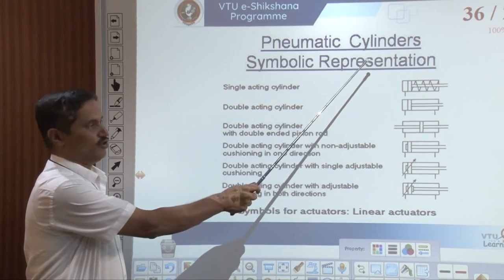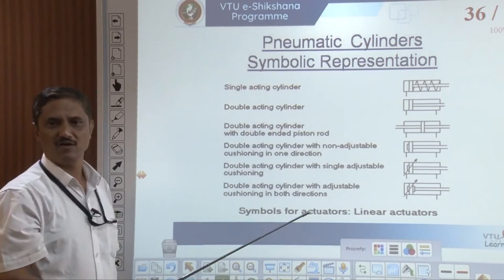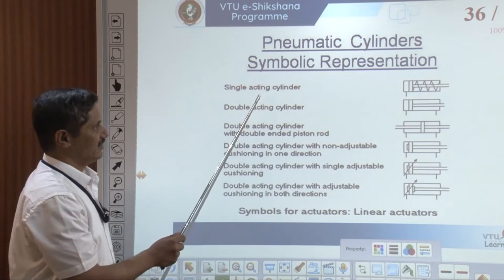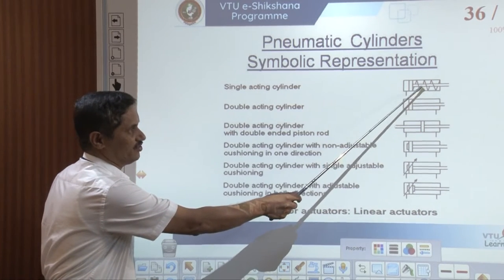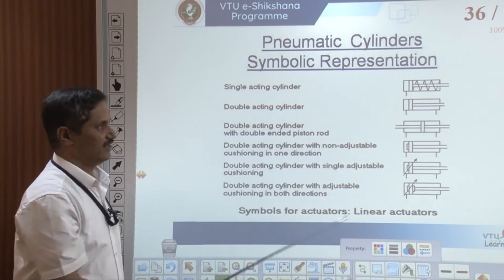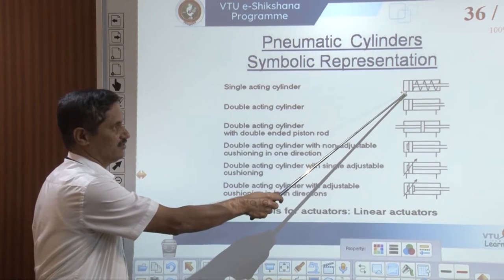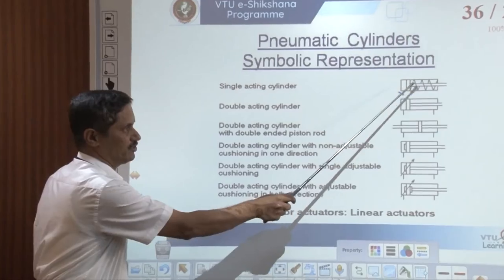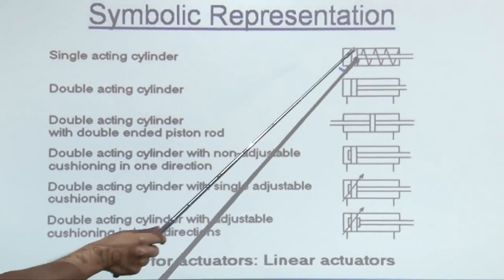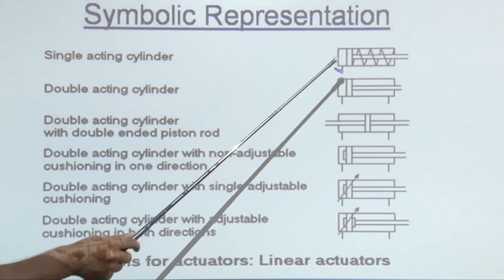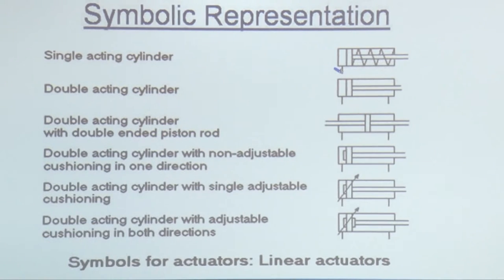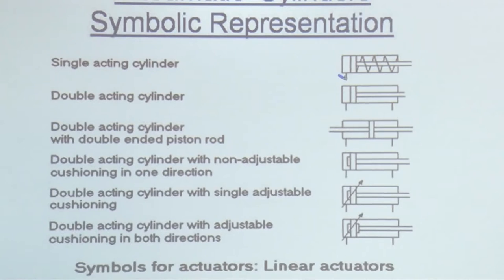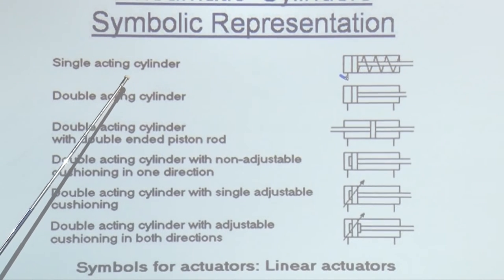In this slide I have shown different cylinders which are normally available and their respective symbols. Single acting cylinder — you can find a spring inside the piston and air enters at one point. Air goes in and pushes the complete piston and spring assembly, and the piston moves forward. When you stop the supply, due to the spring force it returns back. The return force is through the spring. Such cylinders are referred to as single acting cylinders.